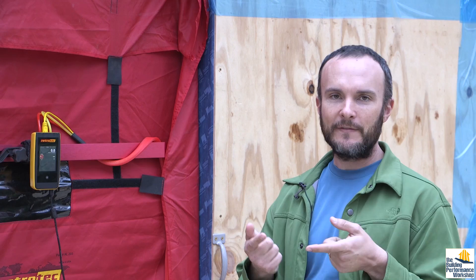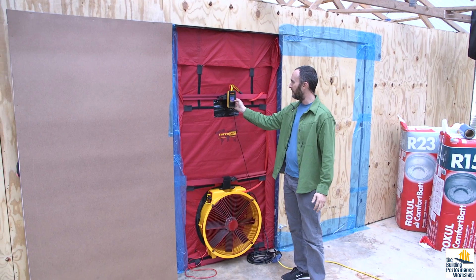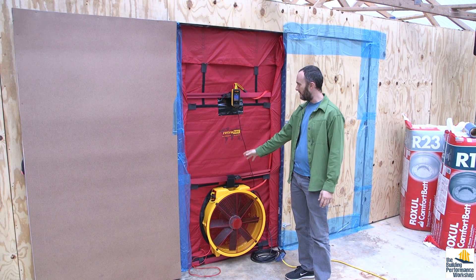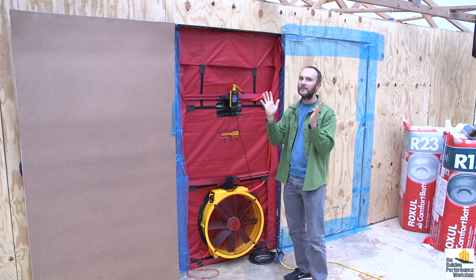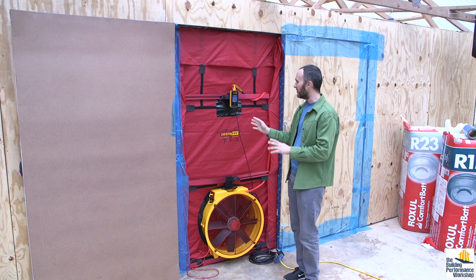So if I want to know what just the insulation is doing on its own, I have to do it before I run the blower door. Now let's set up that RetroTech 5000. Magically, this dry vault is about the same volume and surface area as the TinyLab, and the TinyLab was Passive House airtight. We did a whole bunch of extra stuff with the TinyLab because we were going to expose it to an earthquake and a hurricane at the same time. This is called the highest performance tool shed in the universe — the way I've been branding it — so let's find out. We get our pressure up to 50 pascals on our RetroTech 5000; this thing can go down to less than one CFM, which would be a dream. It's probably not going to do that, so let's find out.